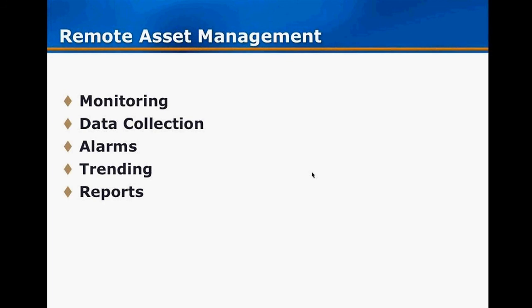For remote asset management, Five Star focuses on monitoring, data collection, alarms, trending, and reports. They monitor primarily flow, and batteries — if a battery drops below 10.5 volts on many meters, it will stop measuring gas or radios will quit talking, so they can detect when batteries need replacing. They look for no-flow conditions with volume alarms so a field engineer can be alerted to give that well attention. Trending helps with batteries too — you can see the trend of battery voltage dropping or recovering with solar charging, and determine if you can get a few more days out of it.